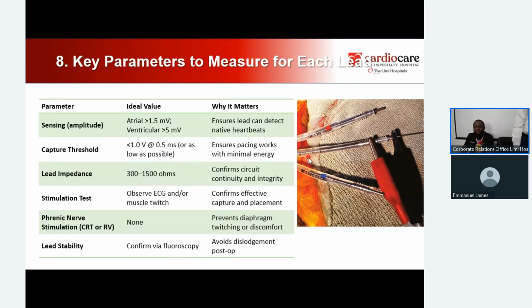So we connect after we have implanted the lead. Now we connect the cable to the end of the lead. If you look at this as being the end of the lead, we take this crocodile mouth and we connect that, black to the tip and red to the ring. Then we connect that to our interrogation device, the pacing analyzer.